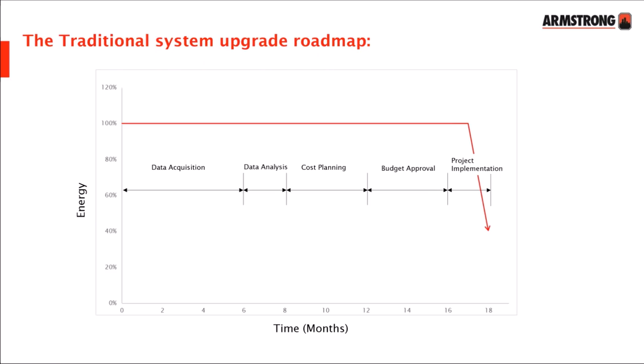What we're saying here at Armstrong Fluid Technology is to follow our roadmap and our pump first approach. So you can see 3 clear phases on the screen. We've got the pump, or pump first, and by replacing a pump you can look to save up to 10% of the energy within that system, and you can start to see savings from day one. And that's the difference between what we're talking about here and a traditional approach of upgrading the entire system from the get-go or the major plant.